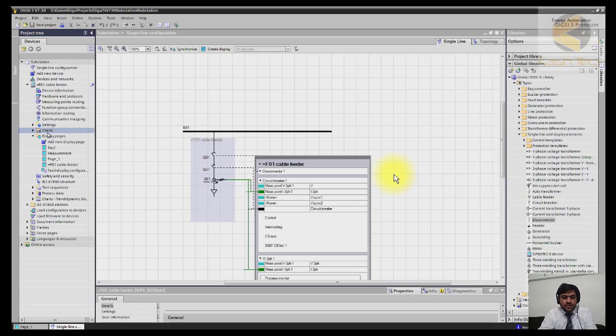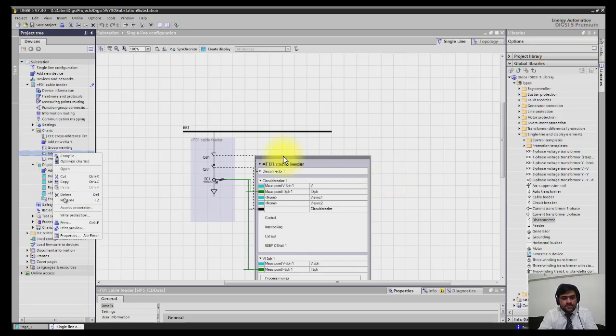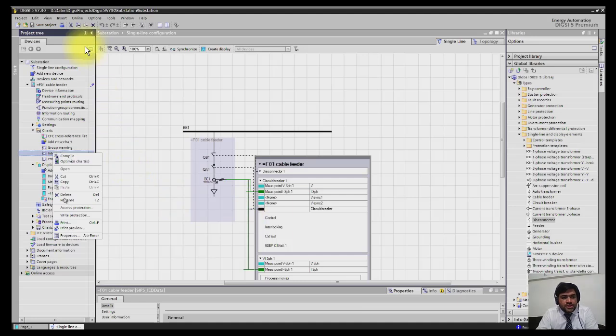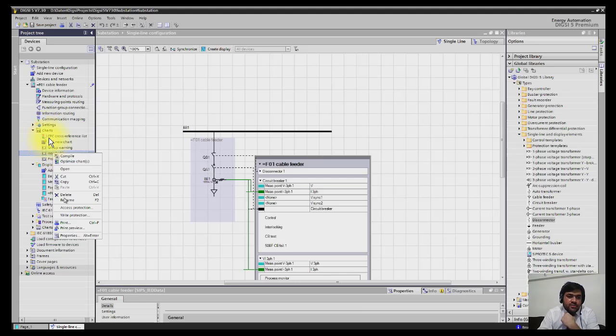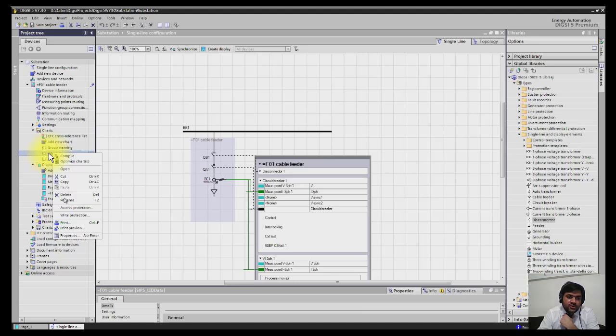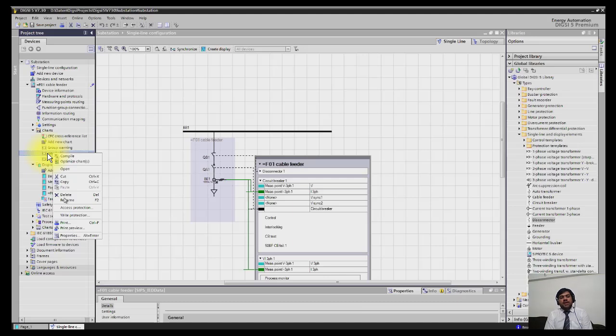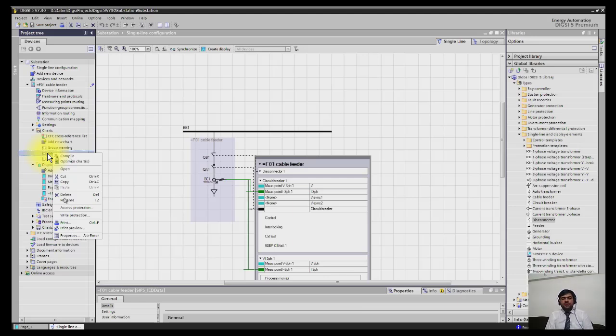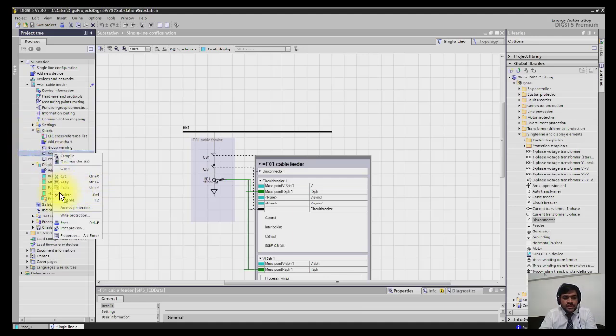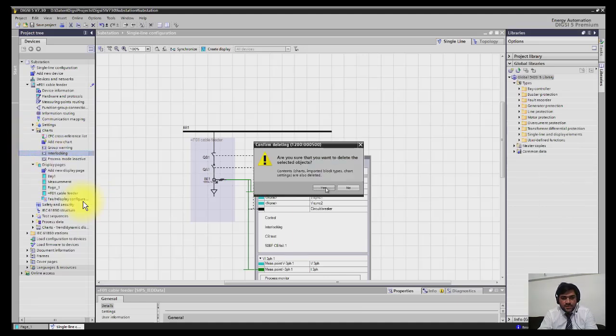We will see how we can draw these interlocks using DIGSI which will be really easy. On the left side in the project tree you can see, you have to click the chart and then you can see for the sub menu some items. Under charts there is already one subgroup interlocks. I have to tell you here that this interlocks are coming as a default file in the relay for double bus bar scheme. So we have single bus bar here and single isolator so it will not work here, so we have to delete this. I will select yes to delete.